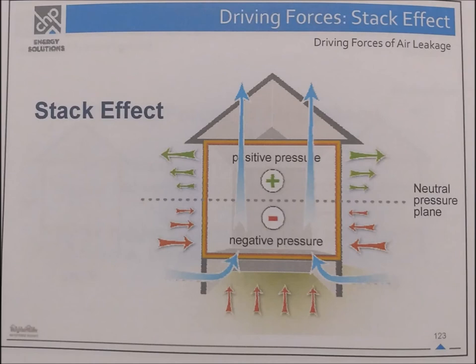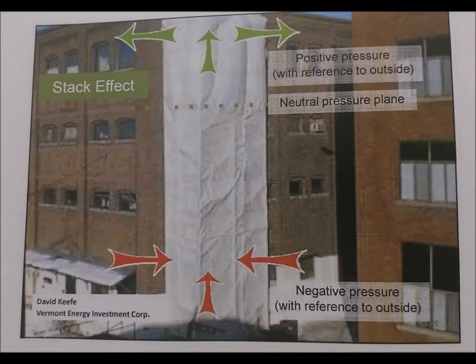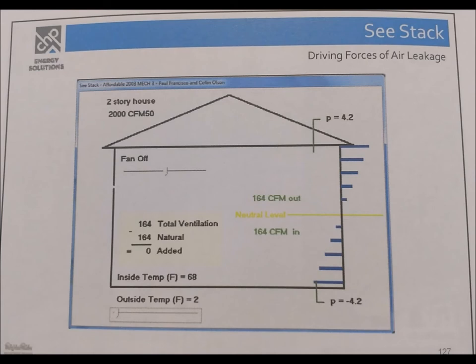Stack effect: Negative pressure is applied at the bottom, passes through a neutral plane, and positive pressure exits at the top — positive pressure with reference to the outside, negative with reference to the outside. Example for a two-story house: 2,000 CFM at 50, fan off, total ventilation at 164 (neutral). Inside temperature 68°F, outside 2°F. Negative pressure at the bottom is negative 4.2 pascals, so the top of the house is pressurized at positive 4.2 pascals.